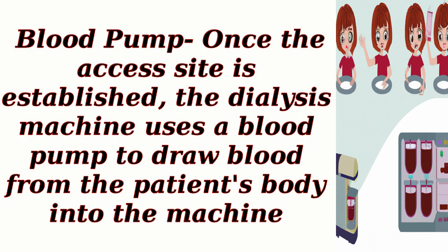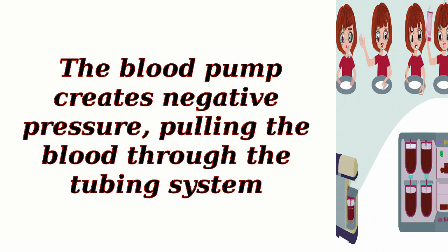Blood pump: once the access site is established, the dialysis machine uses a blood pump to draw blood from the patient's body into the machine. The blood pump creates negative pressure, pulling the blood through the tubing system.